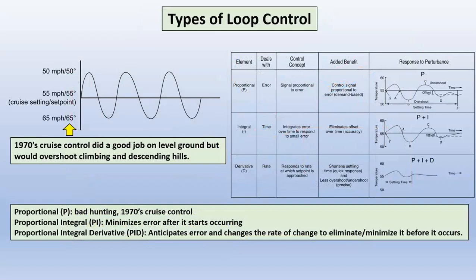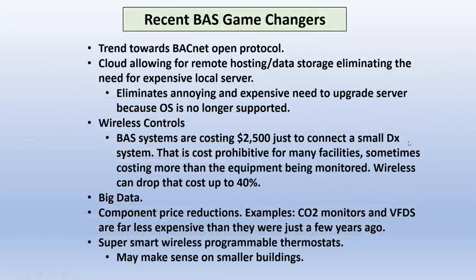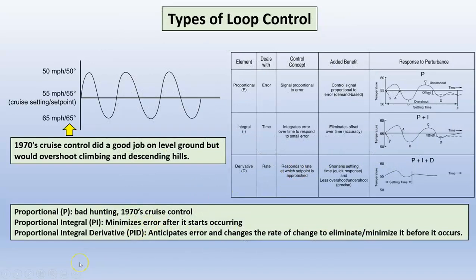All right, loop control. We'll talk about this a little bit, not too deep, but let's see the first example we have over here, the cruise control from the 70s. Kind of an open loop system, and you see how it oscillates. And then we brought up proportional, which had bad hunting. That was 70s. This is proportional control. And then proportional integrative, basically, after the error starts occurring, it starts correcting the error. Oops. And then the latest PID loop, which people are more common with, it anticipates the error in advance and changes the rate of change to smooth it out. So take a look at the graph of that. Much, much better how it's smoothed out there.